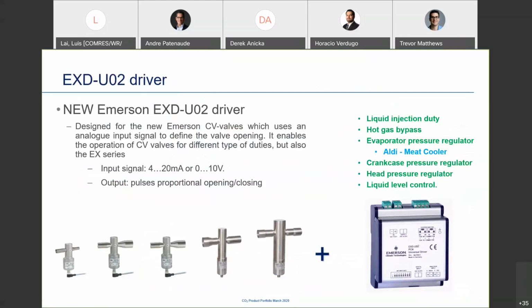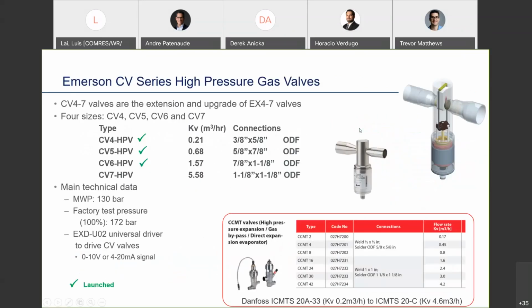It takes a 4 to 20 analog in or a 0 to 10 volt. And you could do any application, hot gas bypass, hot gas reclaim, heat reclaim by managing different valves and so on. From a high pressure control perspective, when you compare our valves to Danfoss, which has really been the market leader, Danfoss, and then you've got Carel is another one.